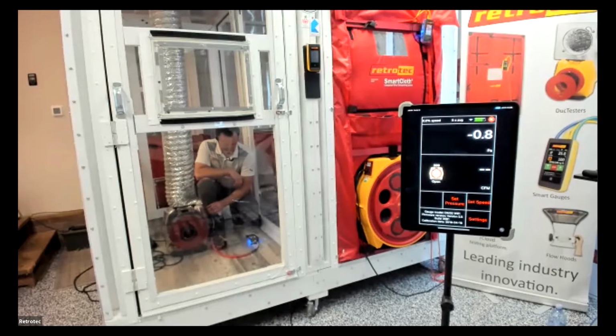Now you notice that when I got to 0, my flow reading went away. There were just 2 dashes there. So what that's telling me is I need to go down a range. The fan is too open. It's not generating enough pressure inside the fan shell to give me a reading. So, well, I did have it on 74 there on the gauge, didn't I? My bad. We'll try that again, but I think it's still going to be a little too open.